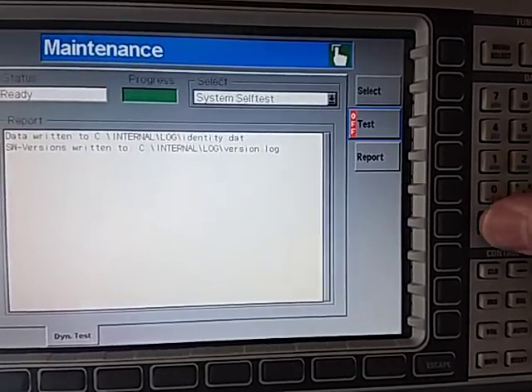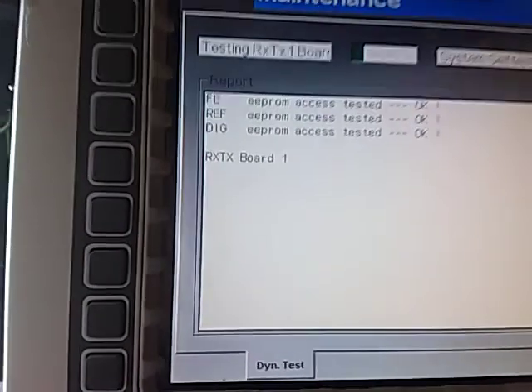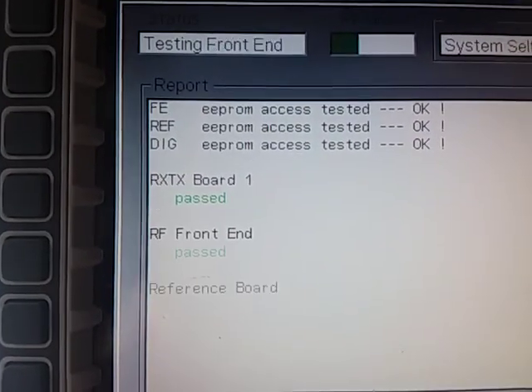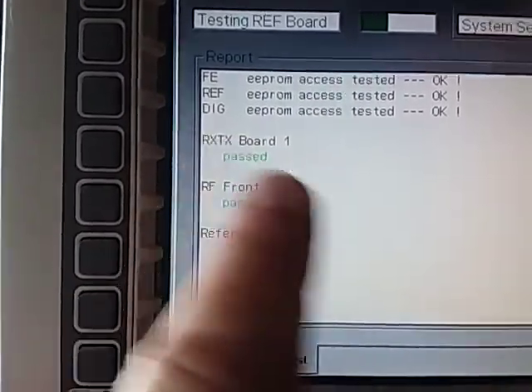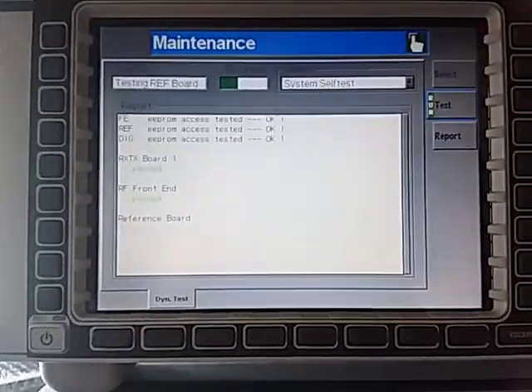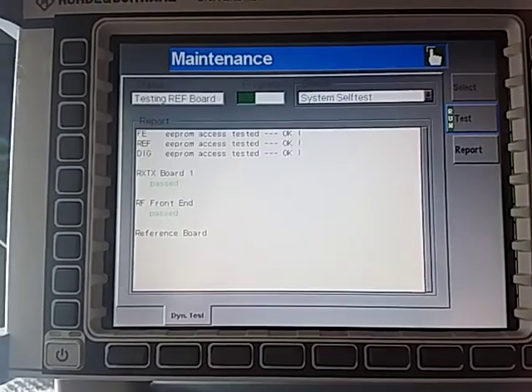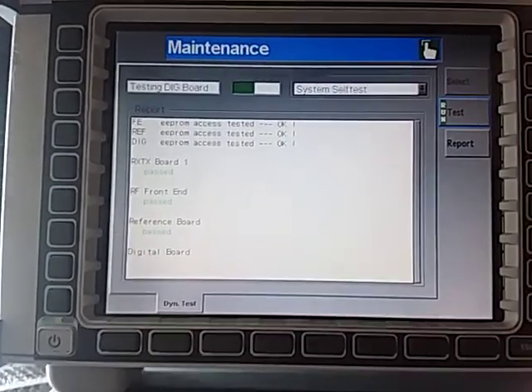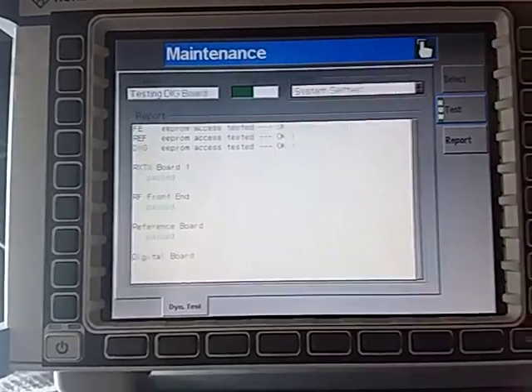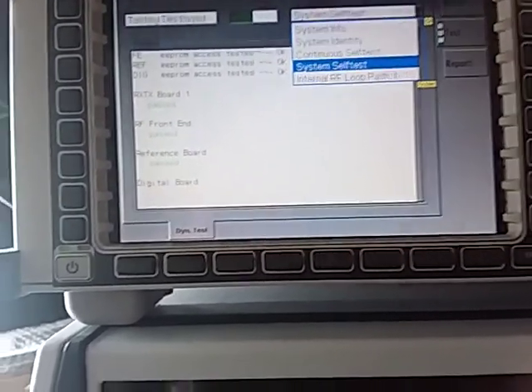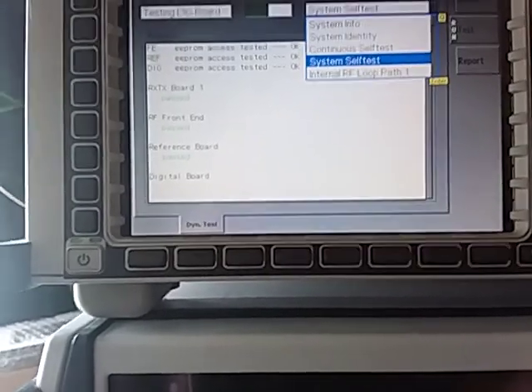The system self-test, this one here will look at each individual module. We'll run that now and it starts off and it does each RXTX board front end. It will go through and do every installed module. Now this is going to take a bit of time with my machine because it's quite loaded. We've got all sorts of options installed in this machine, so it's going to take a long time. I won't bore you with that. Needless to say, it does basic tests on all the modules but it doesn't do any RF path tests.